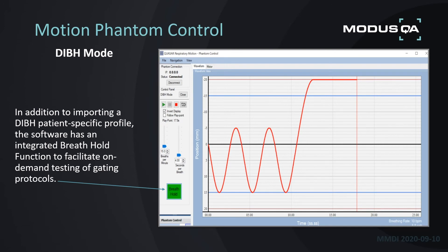A software feature to highlight before the demonstration is our deep inspiration breath hold mode. All three devices have this ability, and it provides efficiency for physicists using a breath hold technique in their treatment protocols. This was a direct response to physicist feedback — they asked for it and we delivered it. It has become a very popular tool within the software, and we are the only phantom manufacturer that includes this with their software.